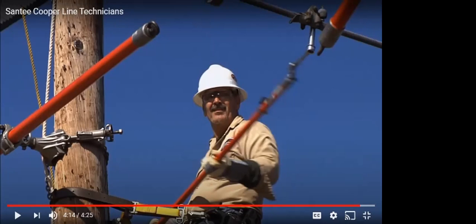How many thousand volts per foot is this stick insulated for? Anybody remember? It's 100,000 volts per foot. All fiberglass products in the industry are insulated to 100 kV, 100,000 volts per foot. So if he's got 3 feet of insulation here, that's 300,000 volts, and he's working on a 115,000 volt line, he's okay.